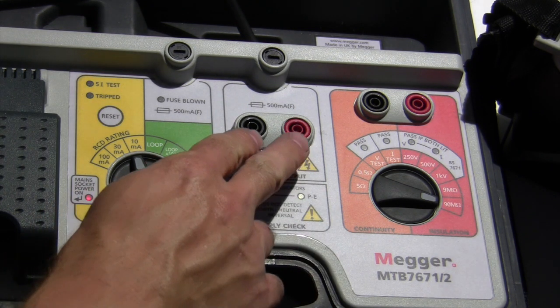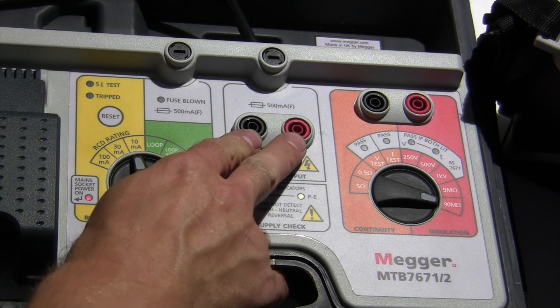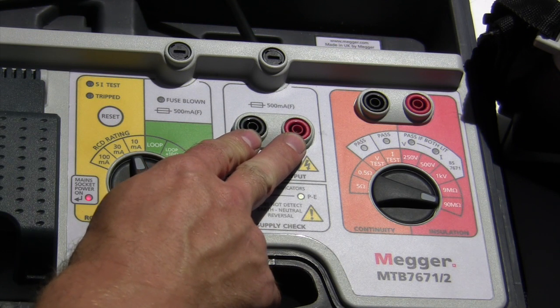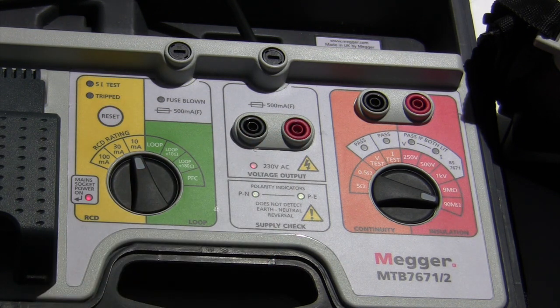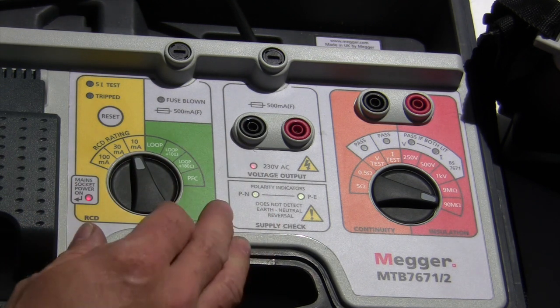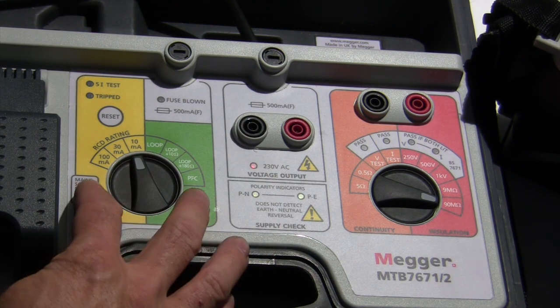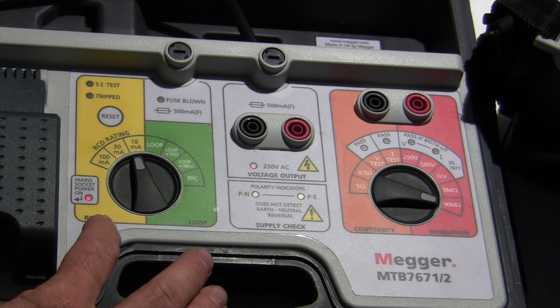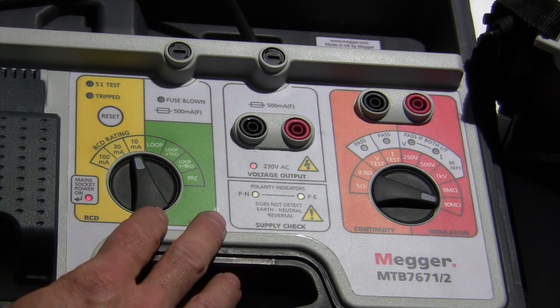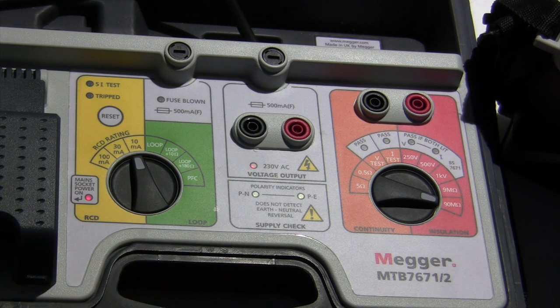We have a voltage test point here where we can plug in our probes to make sure that we're getting somewhere in the region of 220 to 240-ish volts here in the UK. And on this side of the board, this is where we have our live tests. So on the left we've got RCD tests for 10, 30 and 100 milliamp RCDs, and next to that, on this side of the board, we can do our fault loop impedance and prospective fault current tests.